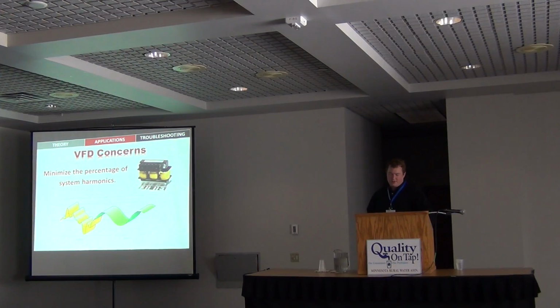An 18 pulse drive nowadays inherently meets something called IEEE 519, which is less than 5% total harmonic distortion, which most utilities have a requirement within their connection standards that says that your plant must meet at the point of common coupling, which essentially is at the secondary side of the transformer feeding whatever your power is from the utility transformer.